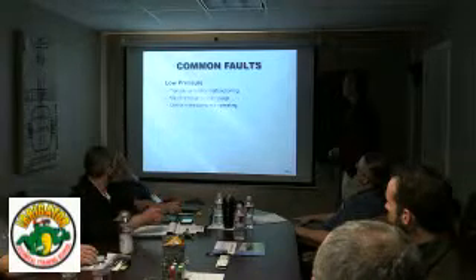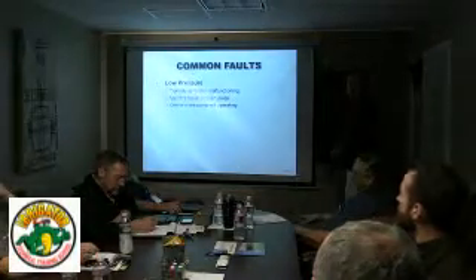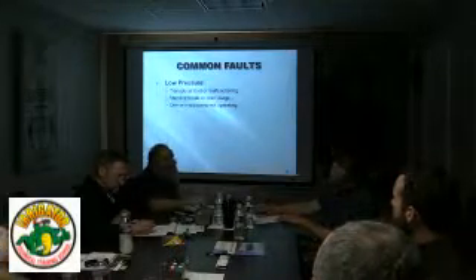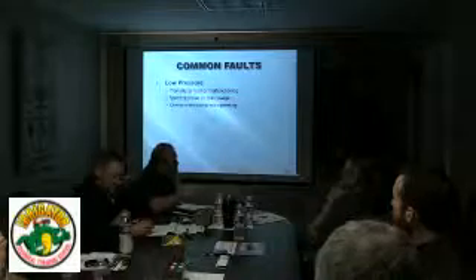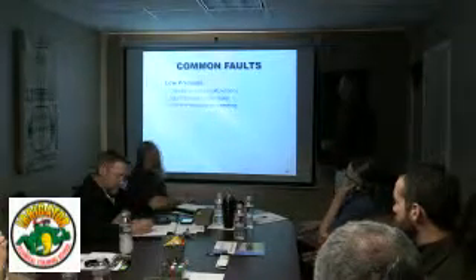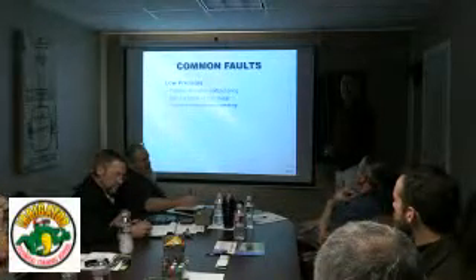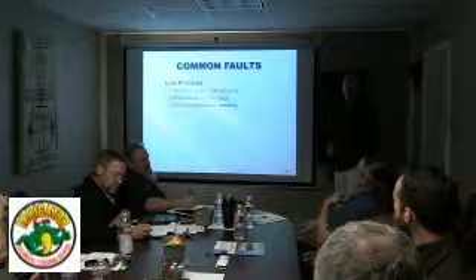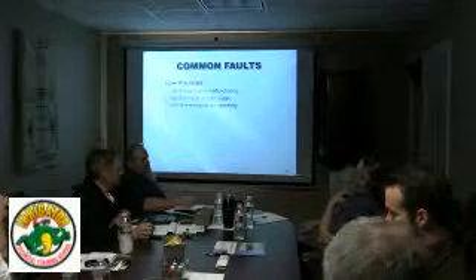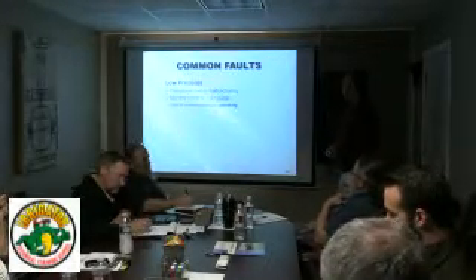So we looked at some of these items, so we'll see what might happen if we do get some faults. Again, on the touch screen, we'll display what the fault is. One you might see is a low pressure fault. Low pressure could be due to a transducer that's bad or malfunctioning. One thing we do on our pump stations and our control panels is we program the drive to use a 4 to 20 milliamp device, so if the transducer completely goes bad, or the wire gets cut for some reason, it drops below 4 milliamps, then we'll fault. But occasionally I've seen transducers partially get frozen and stuck at a certain value or get wet.